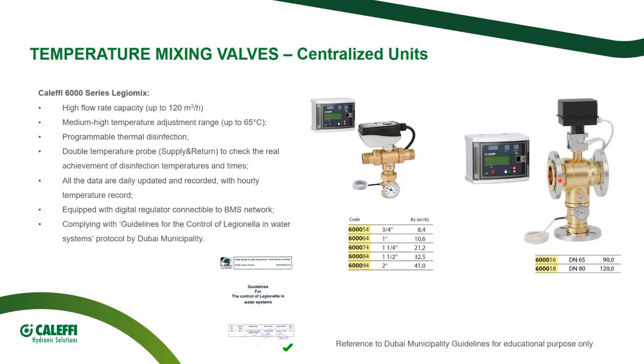So the latest version has a very high flow rate capacity. We are speaking about up to 120 cubic meters per hour. Of course, their temperature adjustment range is medium high because they have to distribute and control the water temperature throughout all the building. They can be programmed for thermal disinfection, and in order to check the real achievement, they are equipped with a double temperature probe.